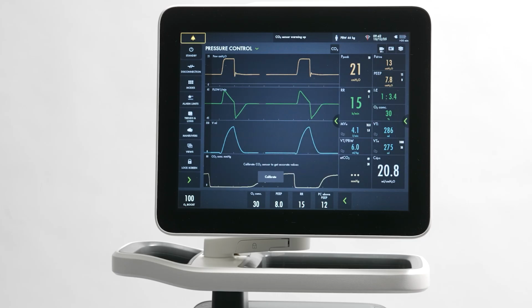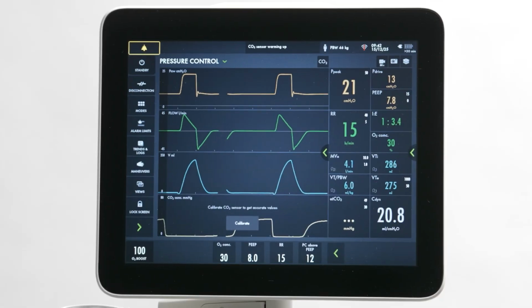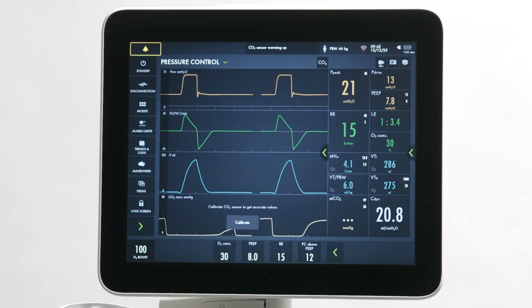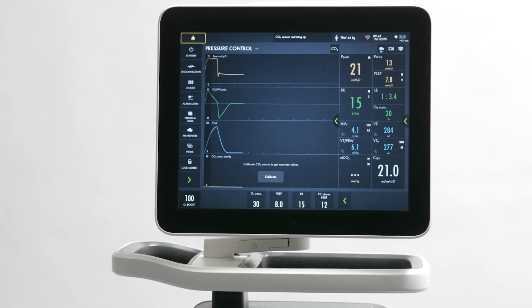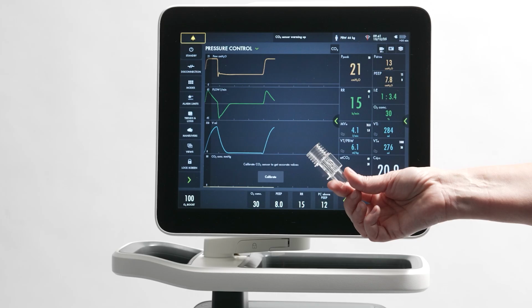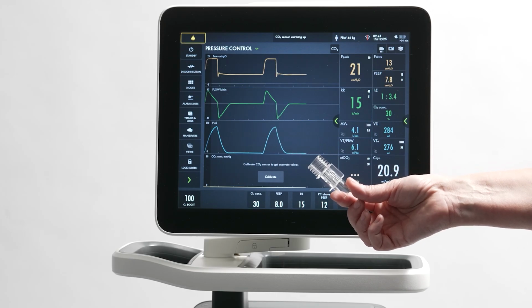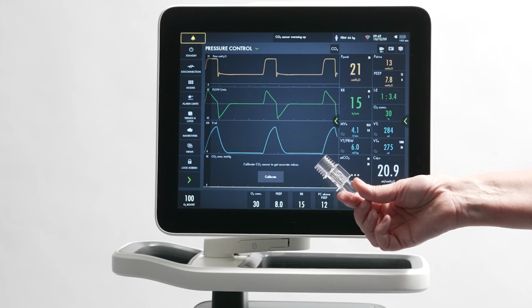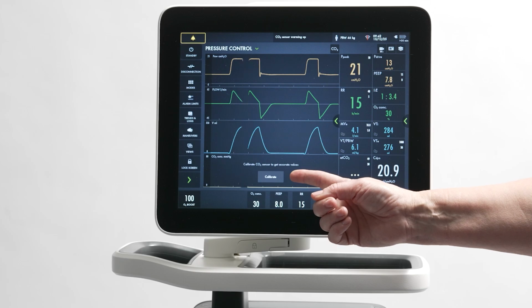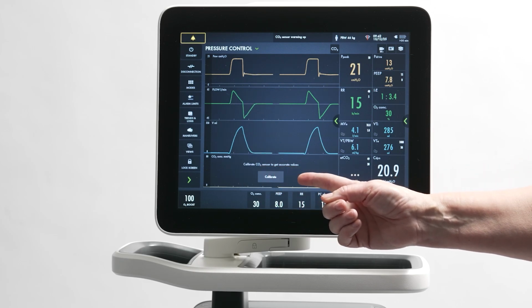We will now go through how to calibrate the sensor during ventilation. The CO2 sensor must be calibrated using an airway adapter. There are two adapters available. The white adapter is for the adult patients and the red adapter is for the infant neonatal patients. If calibration is necessary, a message will appear on the screen.